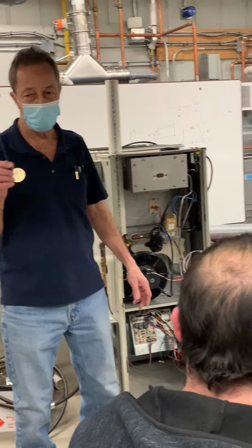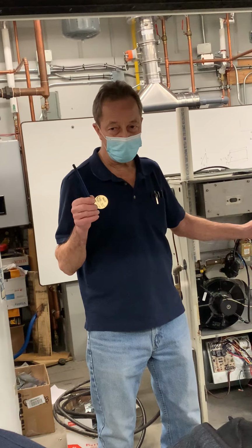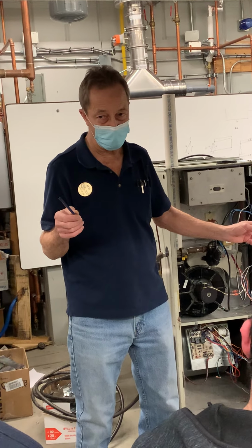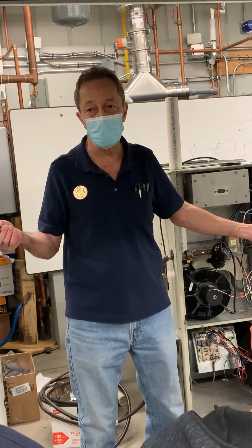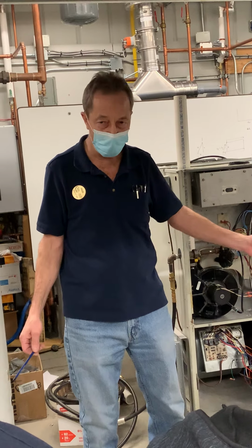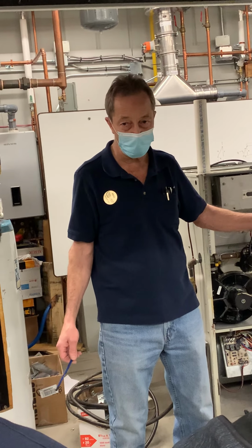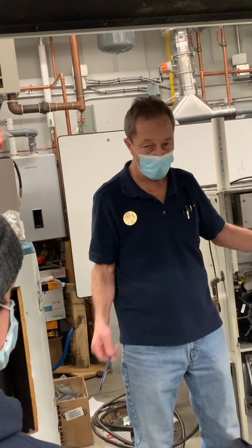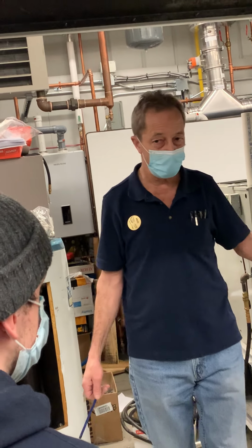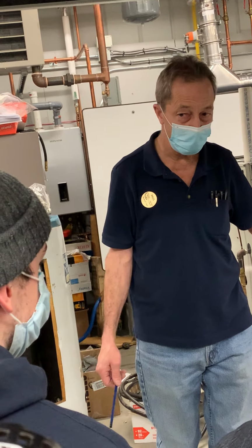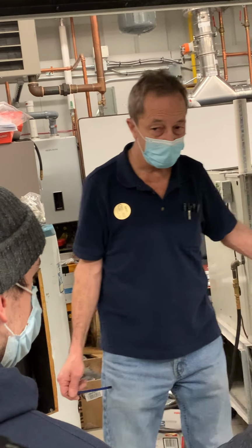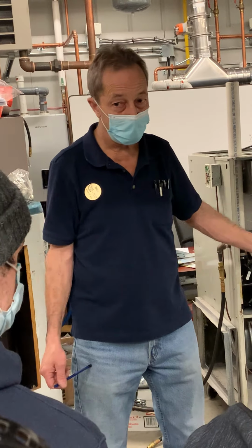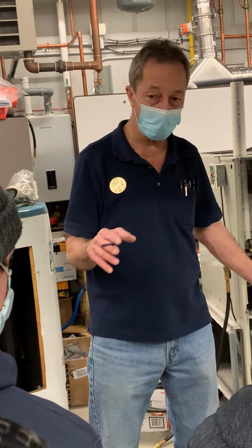So here's what's up. We've got a blocked secondary heat exchanger. We have a flame rollout. How are you going to know if it's a blocked secondary heat exchanger? Yeah, we had the flame rollout, but how do you know it's not because it's overfiring or there's something else going on? How are you going to know it's a blocked secondary heat exchanger? That's okay, you don't have to know the answer yet. When I put it on the test, I want to know the answer then. So what's the answer going to be when you're doing the test?